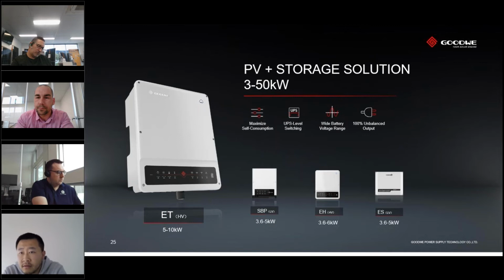So with all of our hybrids, we have UPS level of backup functionality. What we mean by that is when the grid shuts off, our backup will kick in within 10 milliseconds, which qualifies for UPS level switching, as opposed to EPS, which must kick in within 5 seconds.